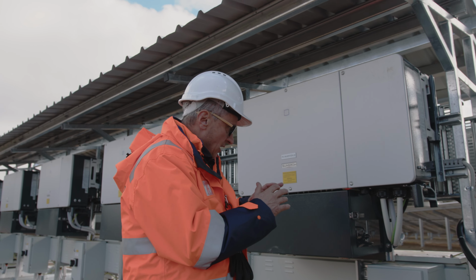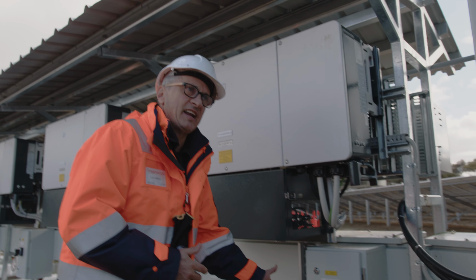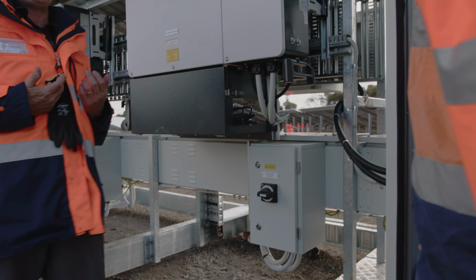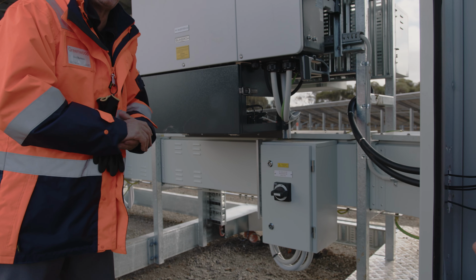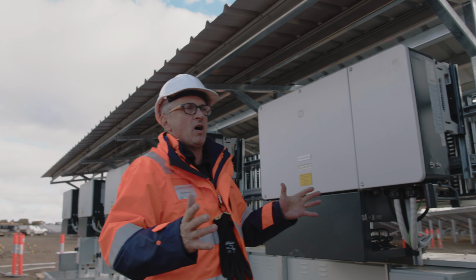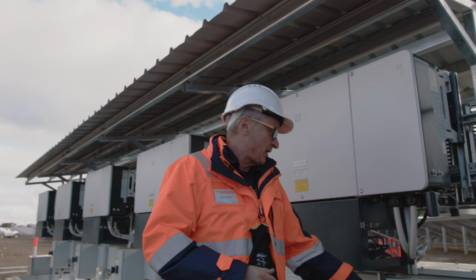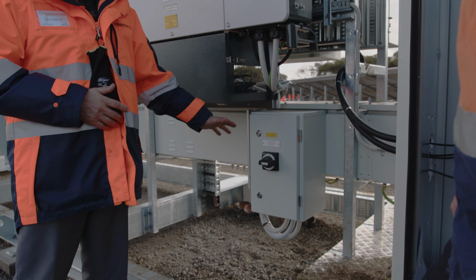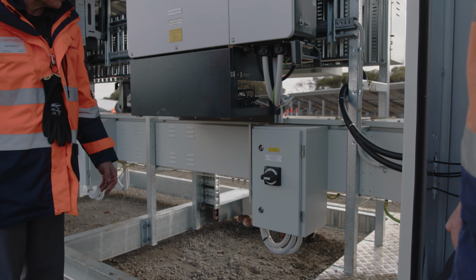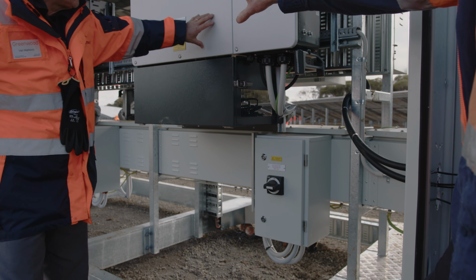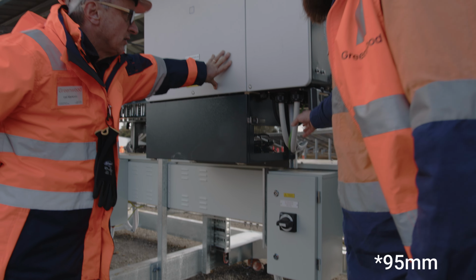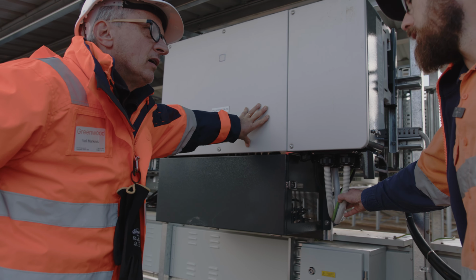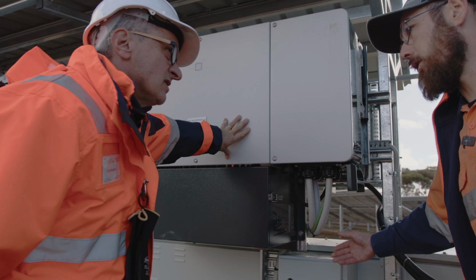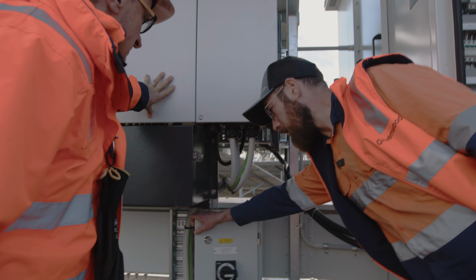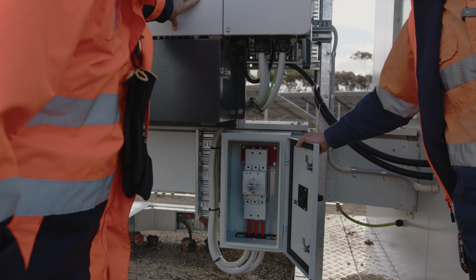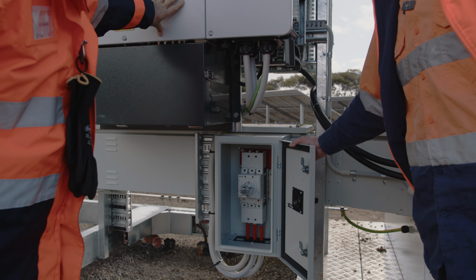Now, AC isolator. When I see an isolator, I assume there's no fault current protection, it just turns off when required. But this is a misnomer because it's multi-use, it's an isolator as well as a circuit breaker. Because we've got the busduct directly behind it, these 90mm cables do not have any circuit protection. So to provide circuit protection as well as a point of isolation, we've got these boxes fitted out with a circuit breaker that is being used as an isolator also.